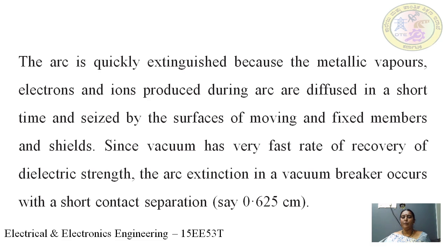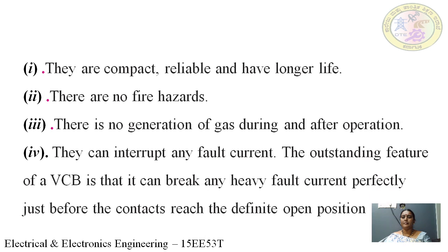Since vacuum has a very fast rate of recovery of dielectric strength, the arc extinction in a vacuum breaker occurs with a short contact separation, say about 0.625 centimeter. Like this it will work.